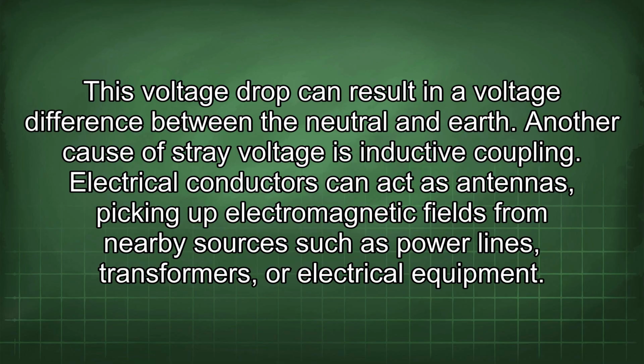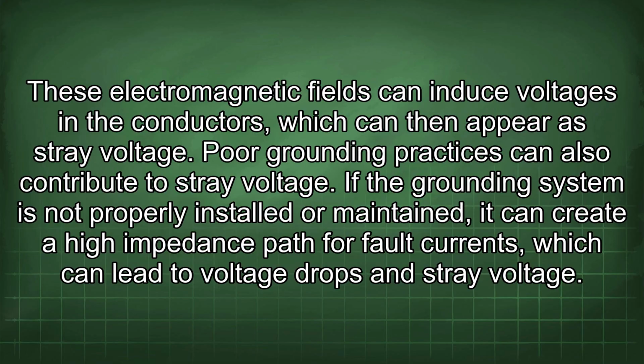Another cause of stray voltage is inductive coupling. Electrical conductors can act as antennas, picking up electromagnetic fields from nearby sources such as power lines, transformers, or electrical equipment. These electromagnetic fields can induce voltages in the conductors, which can then appear as stray voltage.